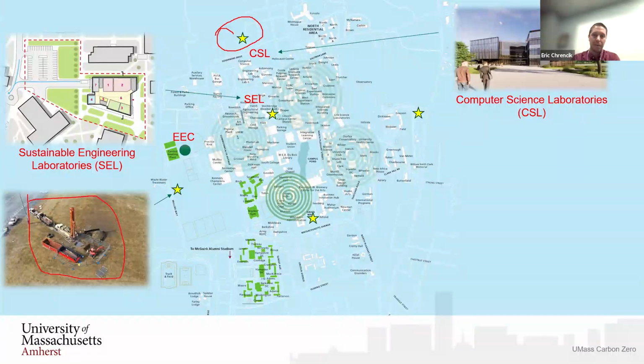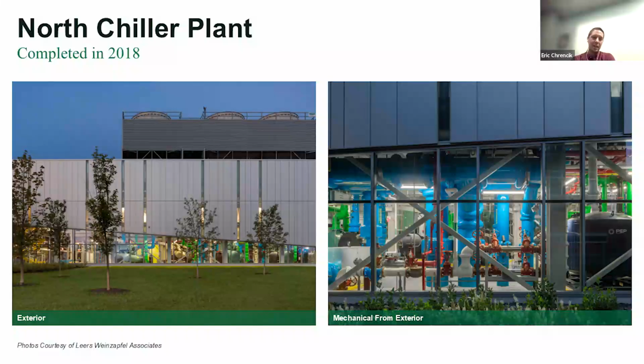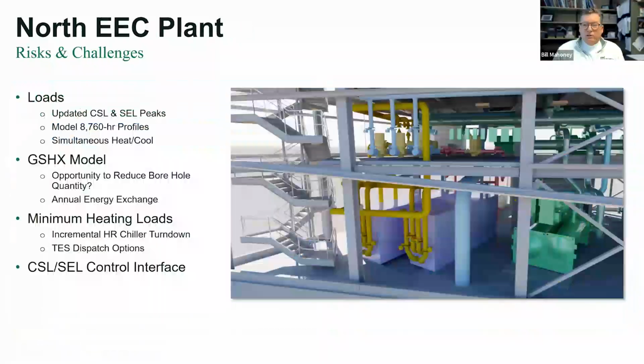We can make a nice little loop. We can leverage the existing chiller bay that was open for a future chiller in the north plant, and we can start a district ground source heat exchanger loop and low temperature hot water system to the north end of campus instead of to the southwest that we were originally looking at. Boom, there's the plant. Left a nice little bay to the figure on the left, one full chiller bay open that you could, in this case, slide some heat recovery chillers into. The full build out, like I was saying, was planned for one more future cooling tower and one more future chiller, but of course the campus has evolved and planning changed over time. Part of that was that we put in a thermal storage tank next to this, which we'll show you, but that allowed them to not install this fifth chiller.